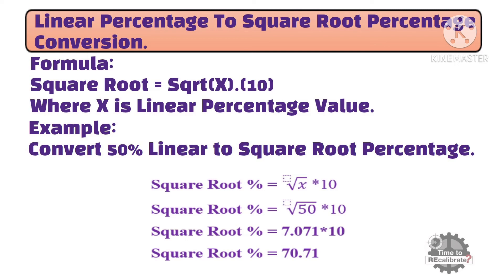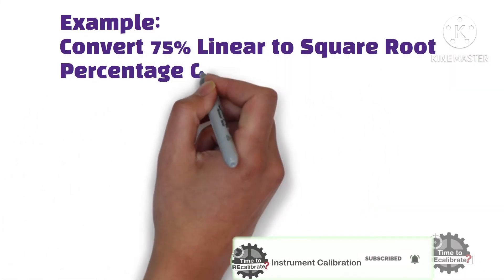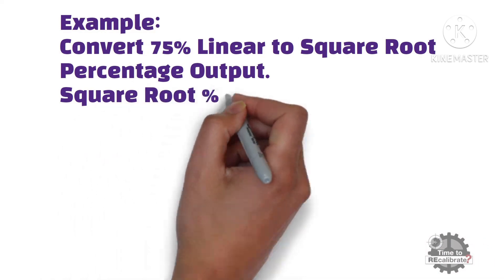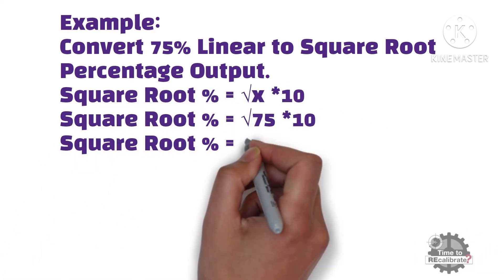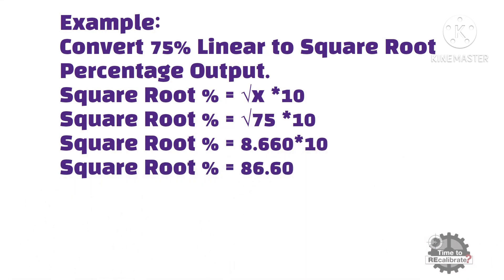It is simple math calculation. Let's go to the next example: convert 75% linear input to square root percentage output. Put 75 into the formula: the square root of 75 is 8.660, multiplied by 10, which gives 86.60. So the square root output is 86.60 for a 75% linear input.